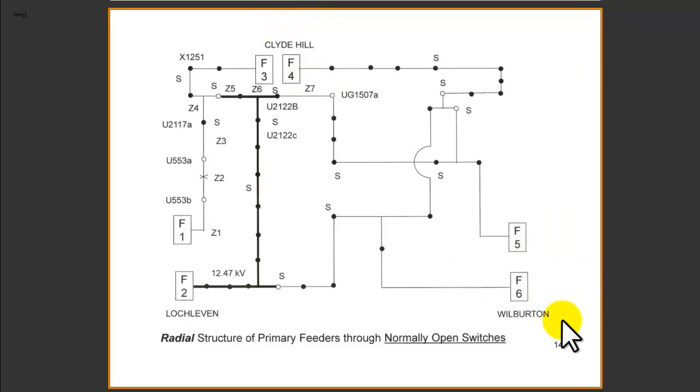The issue here is that if there is a fault occurring at this point, then this segment must be isolated from the network, and then this switch, the breaker here on feeder 1, has to close back so that it will serve 100 customers at this segment. However, this part of the network might have a problem, because if you isolate this and this is closed, you won't have energy fed from this feeder 1 to the rest of the network because it's still in a radial fashion.